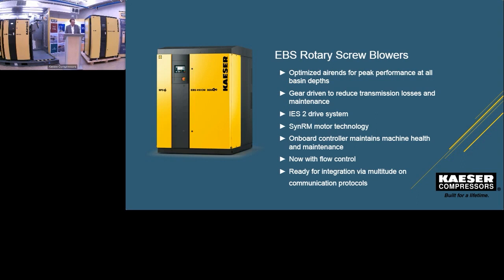And additionally, these screw blowers are a fantastic fit for your aeration process. As I mentioned before, the performance is nice, but they also have an increased control range. These machines come with the VFD, so you have a nice wide control range. And what's really great about a screw blower is that the efficiency curve, if you look at it, is flat from min speed to max speed. So there's really no penalty for speeding this blower up and down.